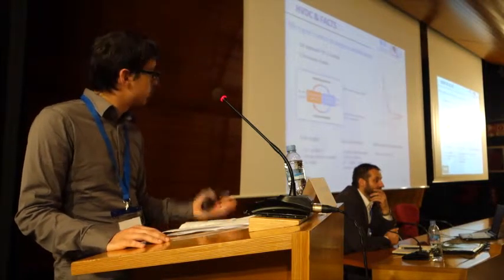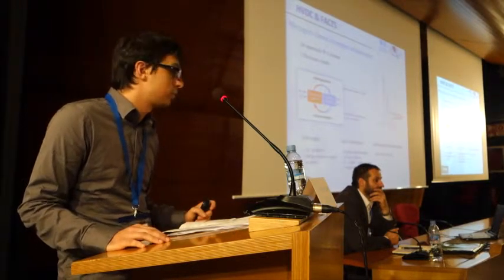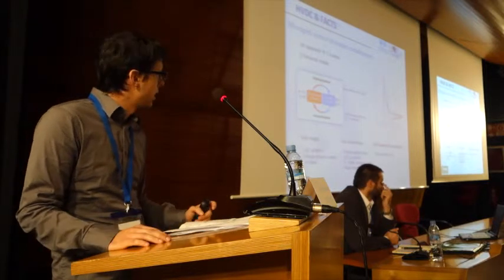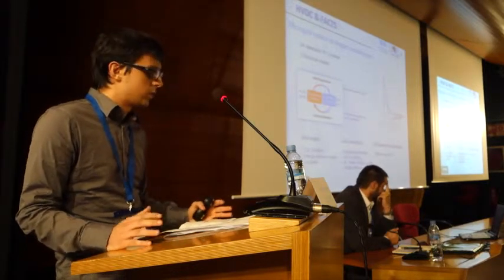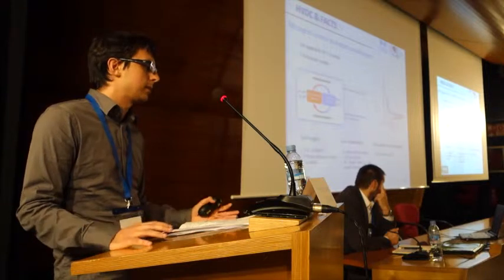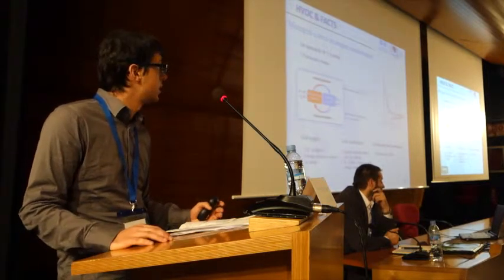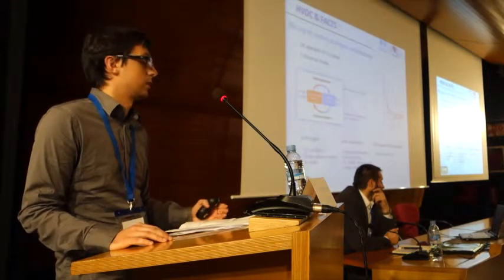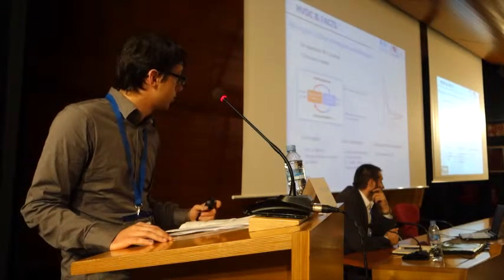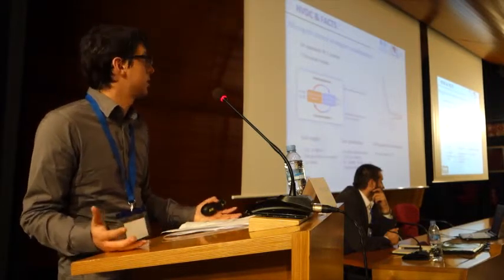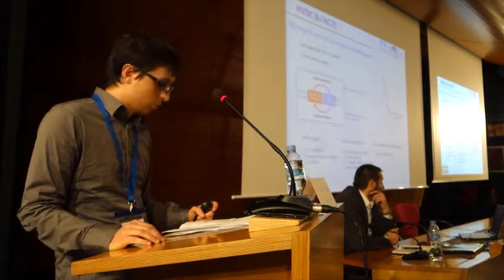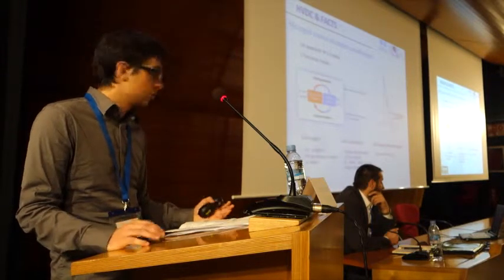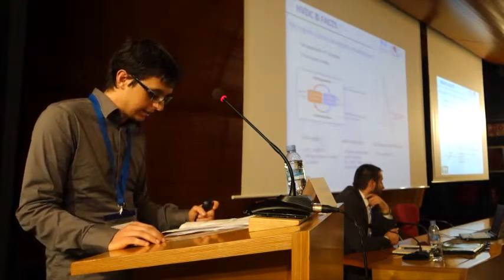It's important to consider, for example, here we have the ITIC curve, which is a regulation that tries to define the maximum and minimum voltages that can be supported, in this case, by an informatic load. But we can extrapolate these results to any load and use them as thresholds for the AC side.